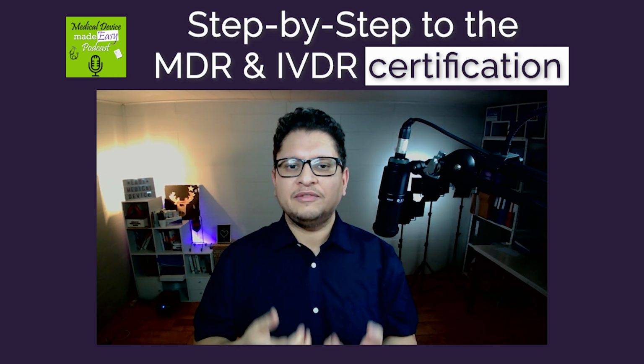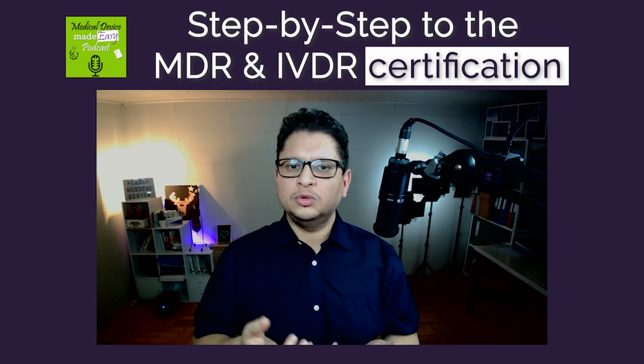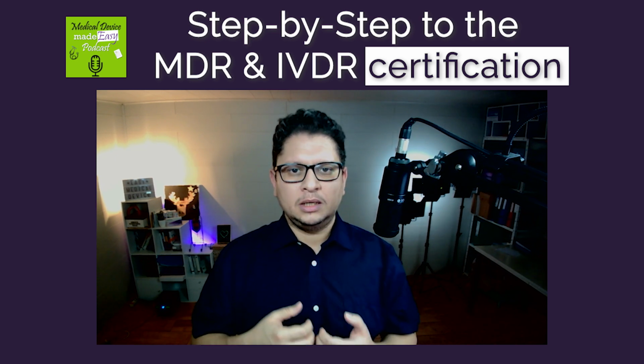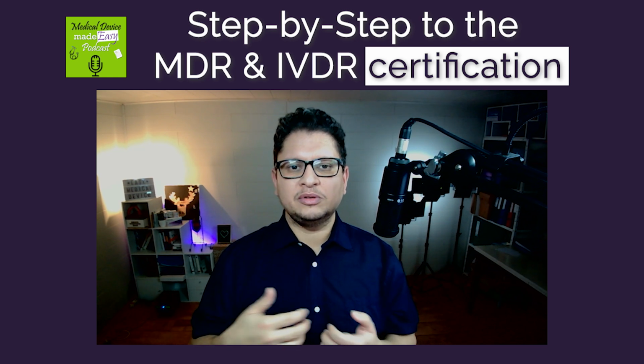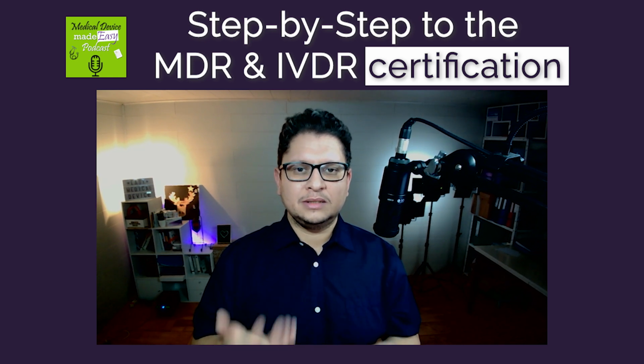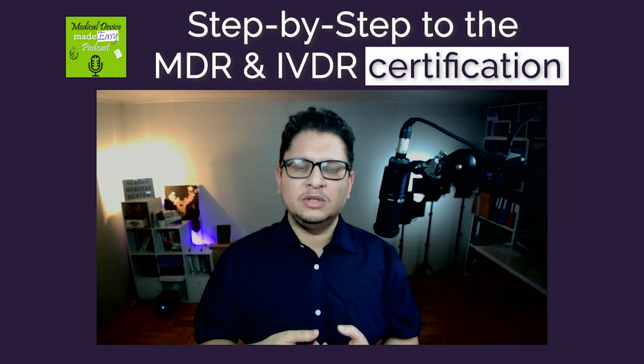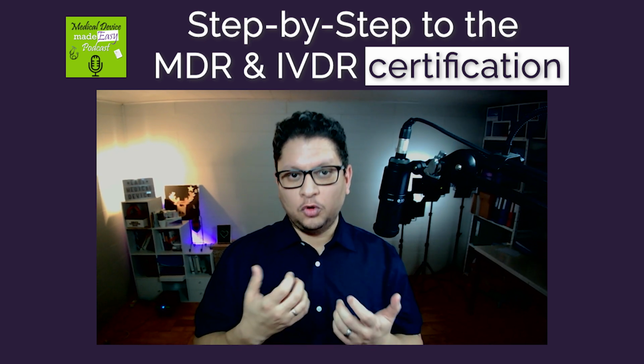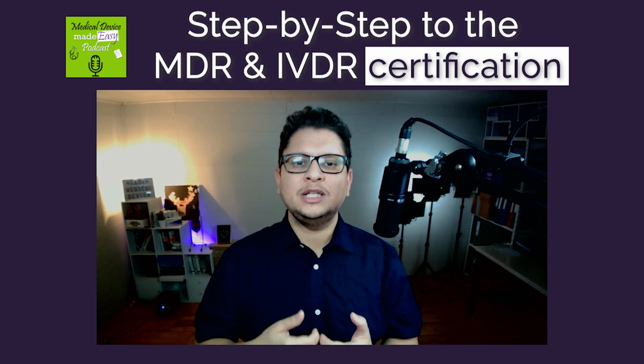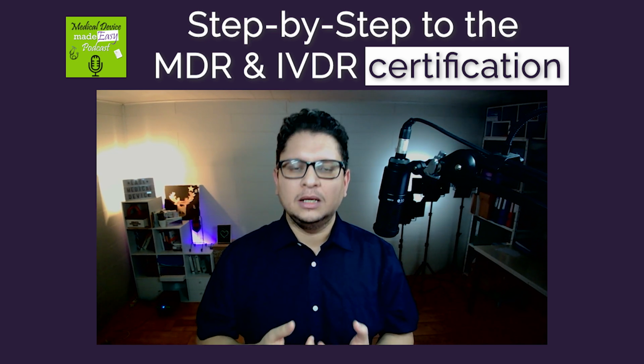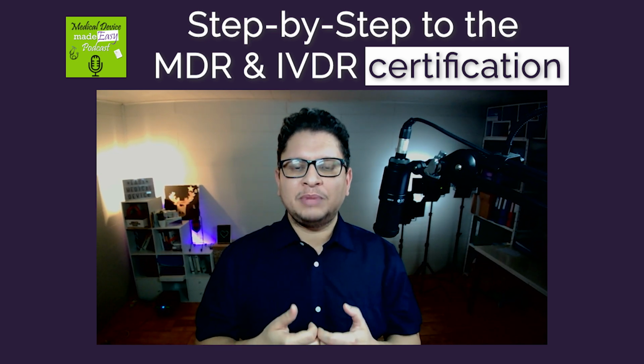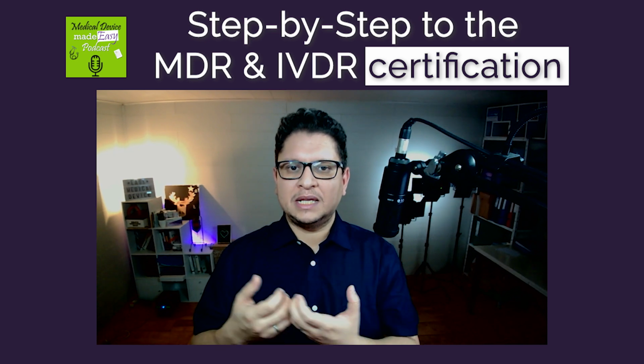And at the end, you have also to provide an answer in terms of the fact that first, yes, your device is safe and performant, but also, do you need a post-marketing clinical follow-up? This is the next step. This is something that is demanded by the EU MDR. You have for sure for every device to create a PMCF plan, not the PMCF study, the PMCF plan, which will say, do I need a PMCF study or not?